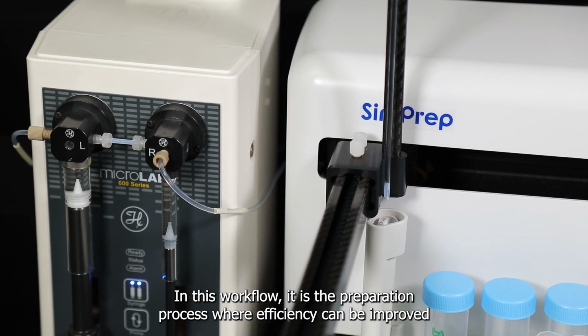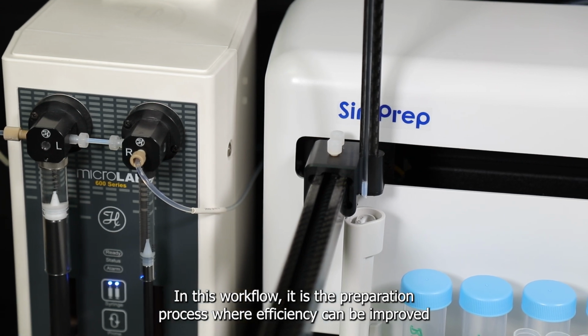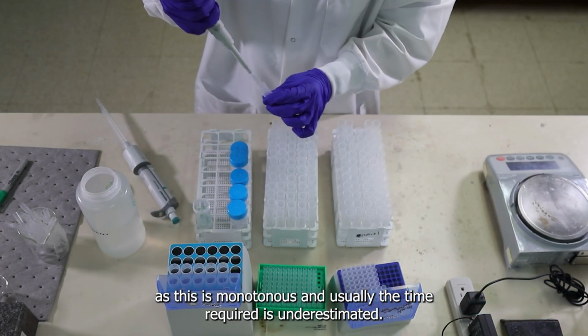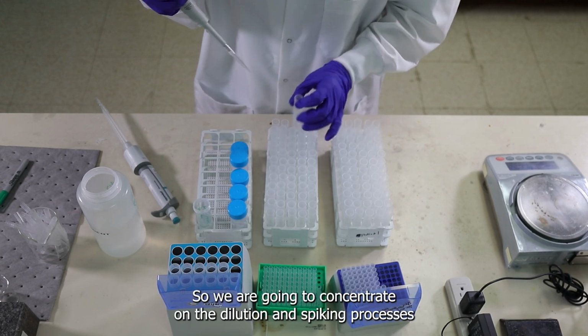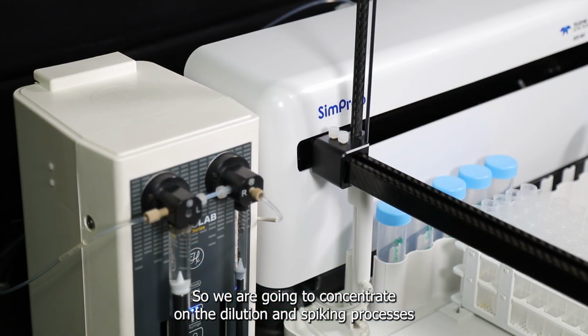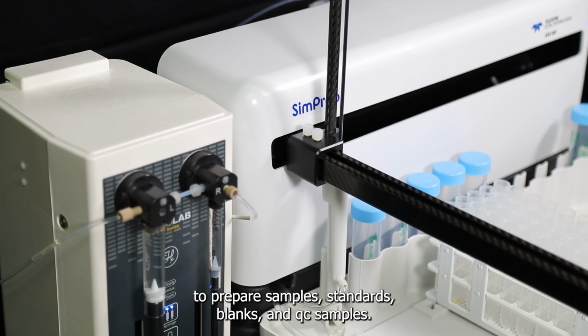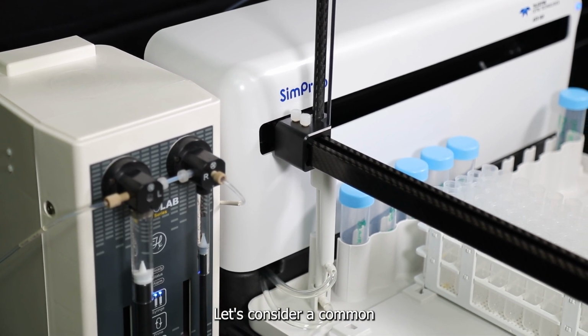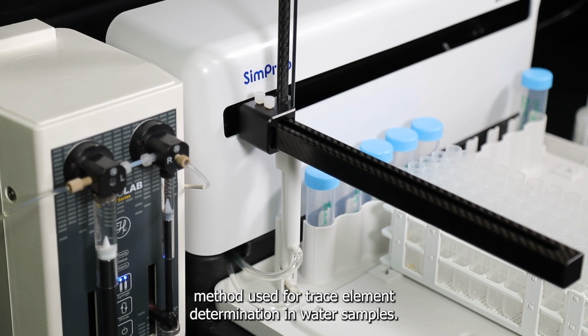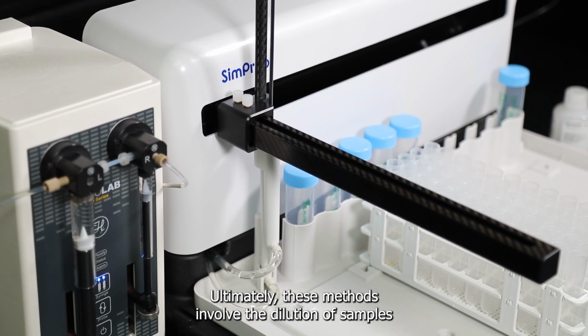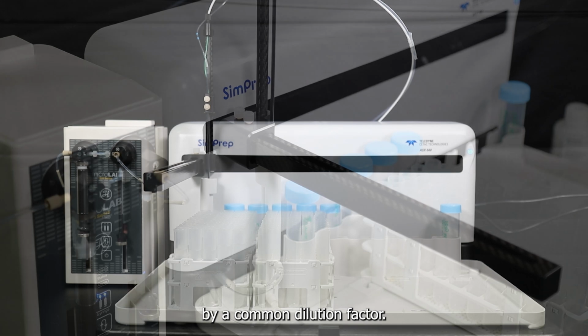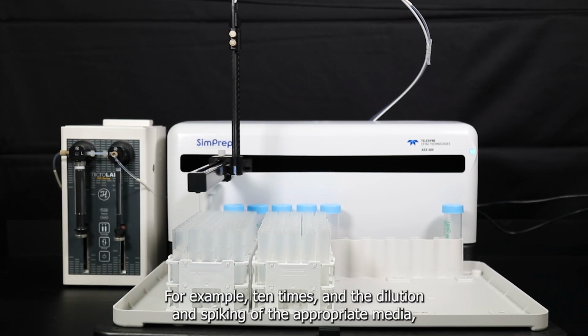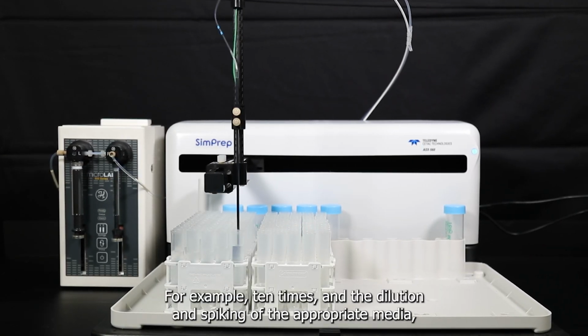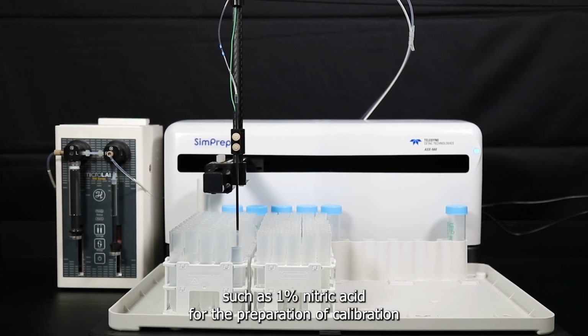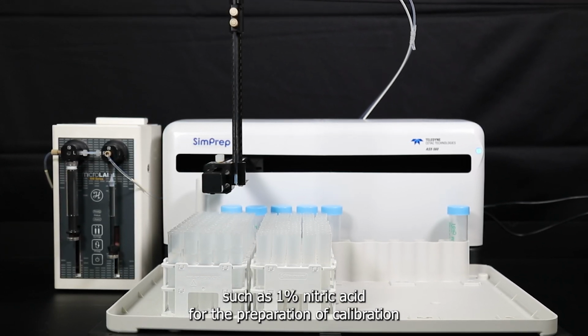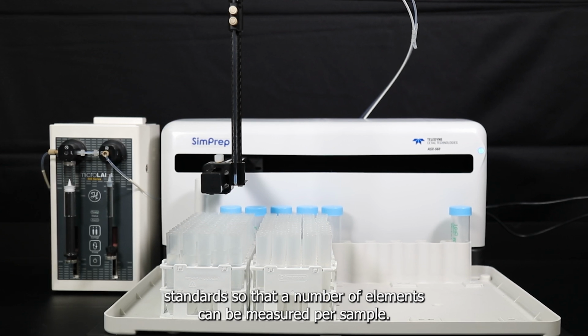In this workflow, it is the preparation process where efficiency can be improved, as this is monotonous and usually the time required is underestimated. So, we are going to concentrate on the dilution and spiking processes to prepare samples, standards, blanks, and QC samples. Let's consider a common method used for trace element determination in water samples. Ultimately, these methods involve the dilution of samples by a common dilution factor, for example 10 times, and the dilution and spiking of the appropriate media, such as 1% nitric acid, for the preparation of calibration standards, so that a number of elements can be measured per sample.